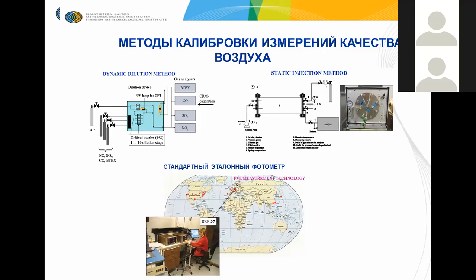laboratories. So basically for gas pollutants, there is most often two main methods. There is this kind of, it's called a dynamic dilution method. It's based on, of course, you have to have the primary standards for each gas concentration, and then with this method you have a diluter that is highly accurate, you can change the flows with that, and of course you have to have traceable flow measurements also to ensure that the flow meter is traceable itself. And this dilution method is then connected to the different kind of gas analyzers for the calibration.